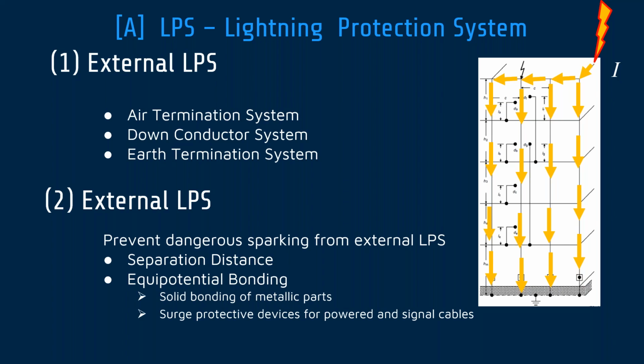So that's the one side. However, now when we're talking about this equipotential bonding, we do not require transfer of energy, transfer of joules. The lightning current's got its path. It's going down to ground. It is the voltage that's rising as a result of that current going down to ground that's causing a problem. So our surge arrestor needs to short the live side and the earth side, neutral side of my medium voltage or low voltage system, my communications cables.